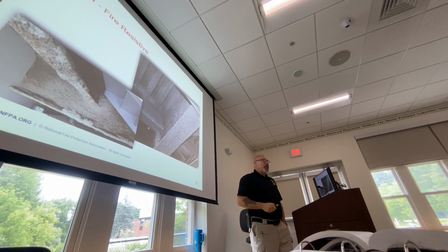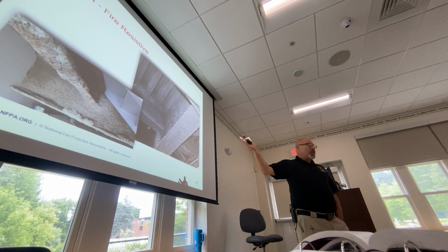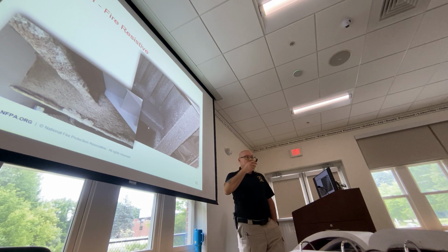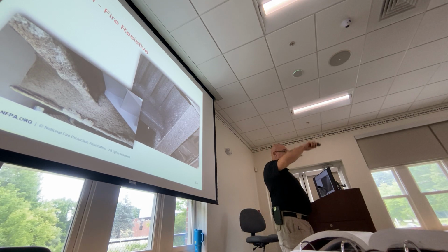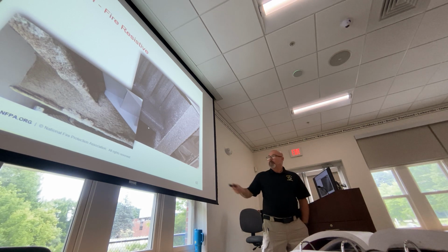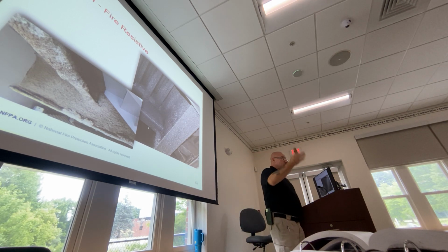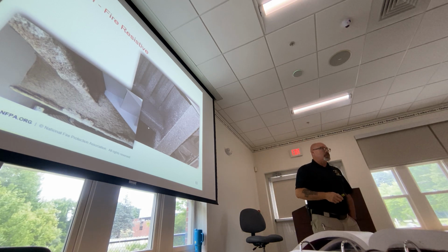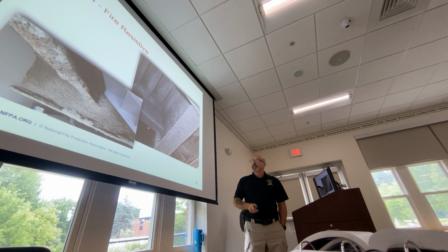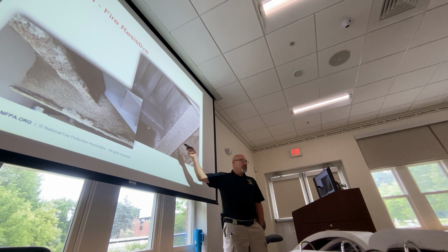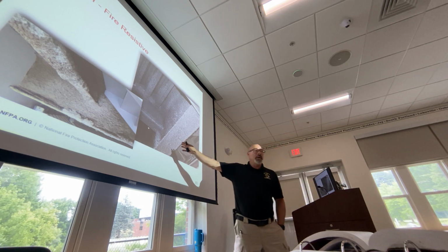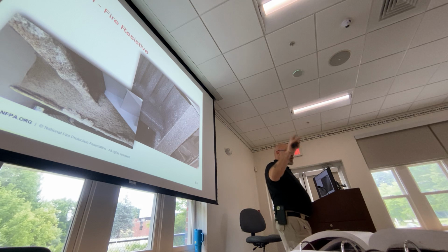So fire inspections are very important during construction like this. Eastern Maine Medical Center, when they built the building in between all the buildings, I was there once a week. Maine Medical Center, we had crews there once a week for the 7-story building they just got done doing. And before they closed ceilings, we were inspecting that. We would inspect it once they sprayed it to make sure that they had all of the coverage.